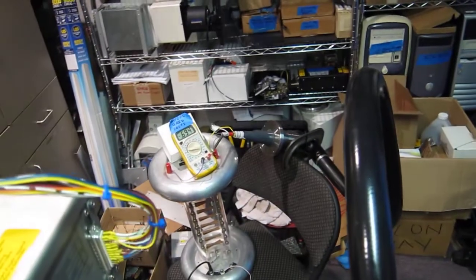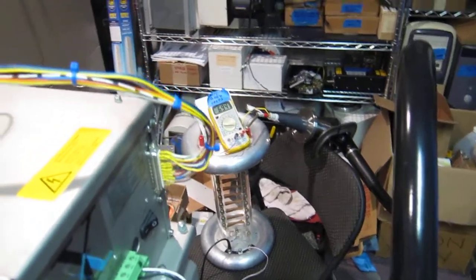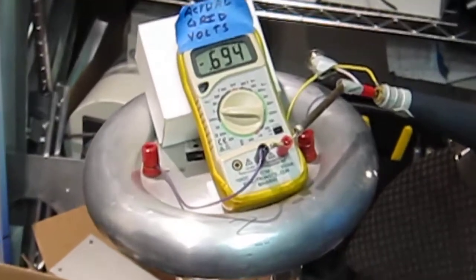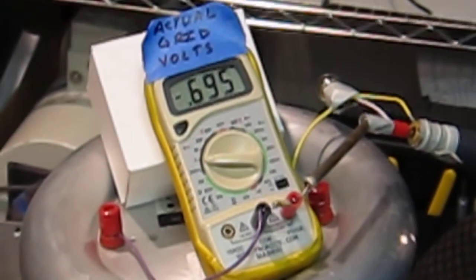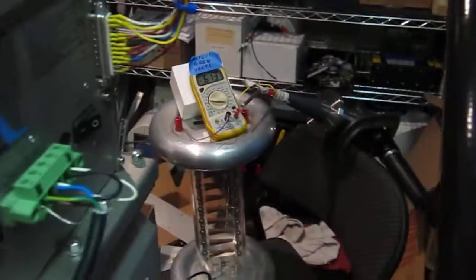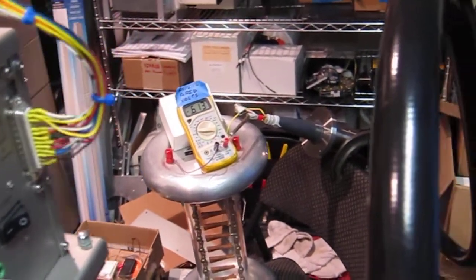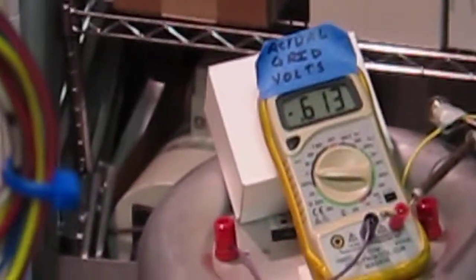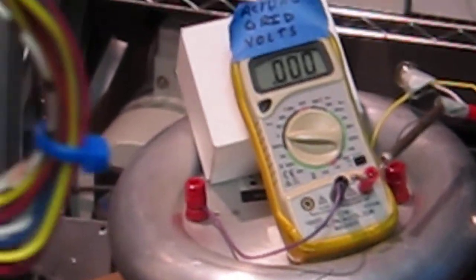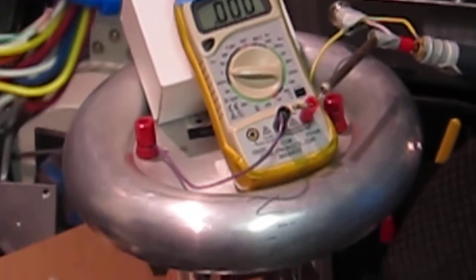So now I turn the filament off, and I can turn the high voltage down with this knob right here. Disable the kilovoltage, the high voltage. Disable the milliamps. And inhibit the grid voltage. Open the interlock, which would be like opening the door to the X-ray machine.